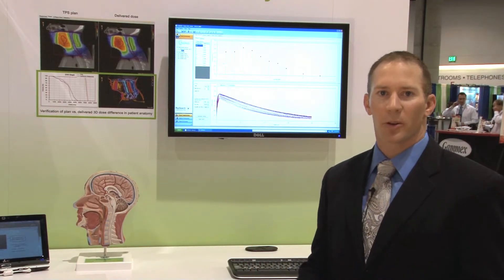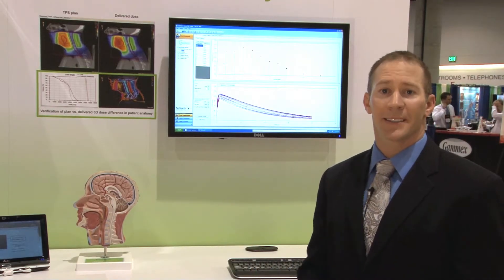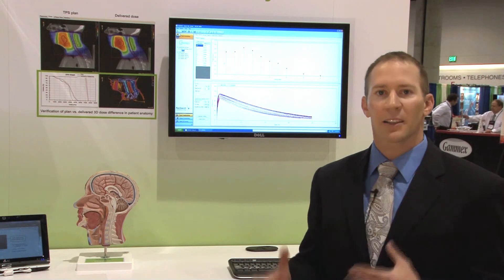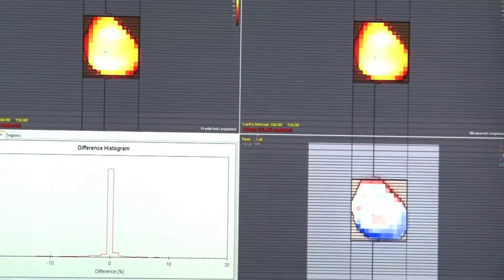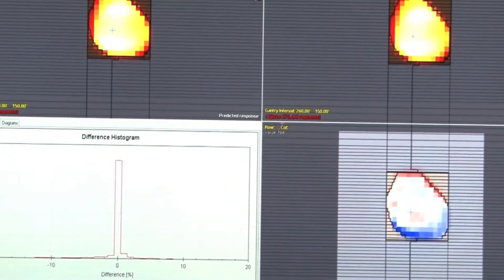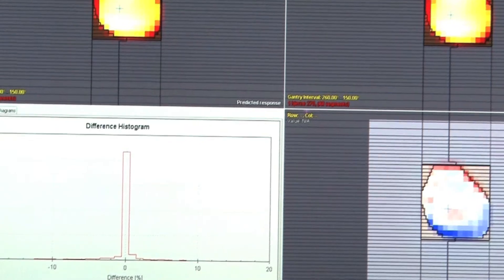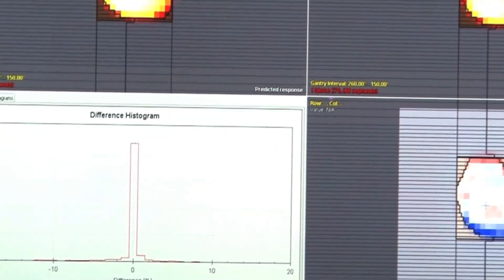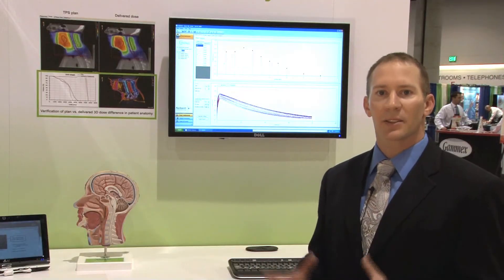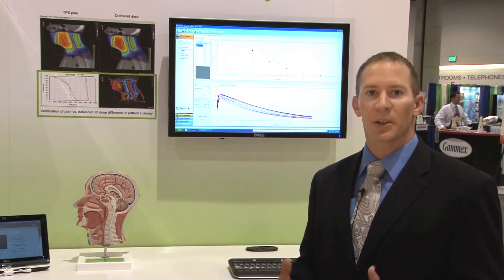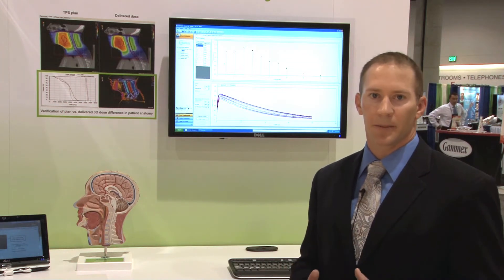The next component of the product is the actual measurement physical validation. We uniquely measure 20 millisecond MLC positions and integrate that into gantry positions, which allows us to get an appropriate measurement of the plan.